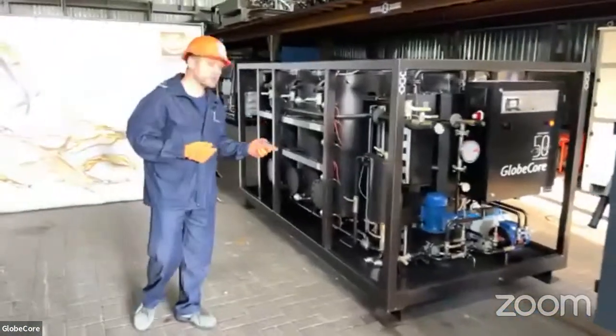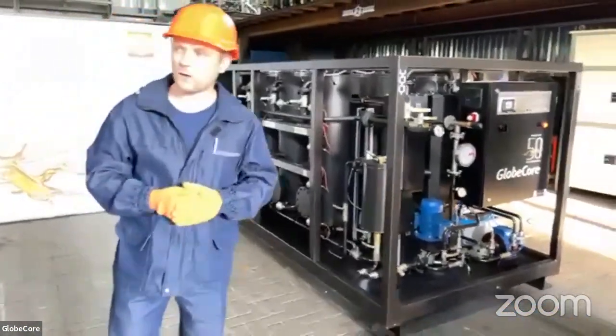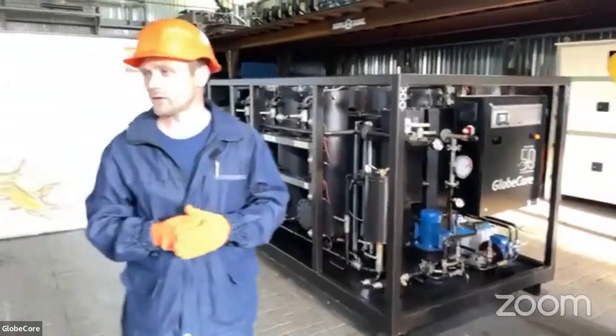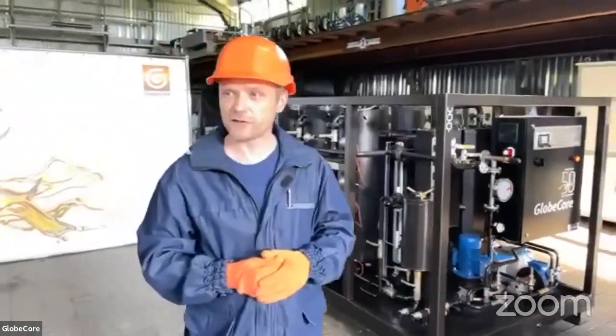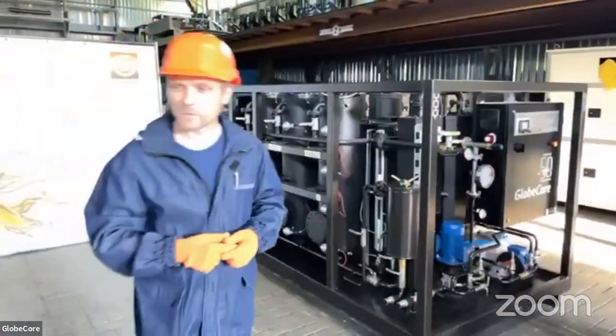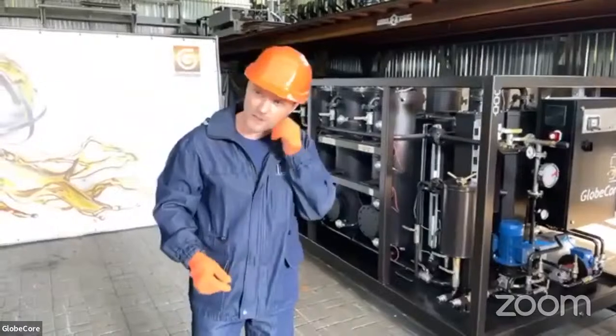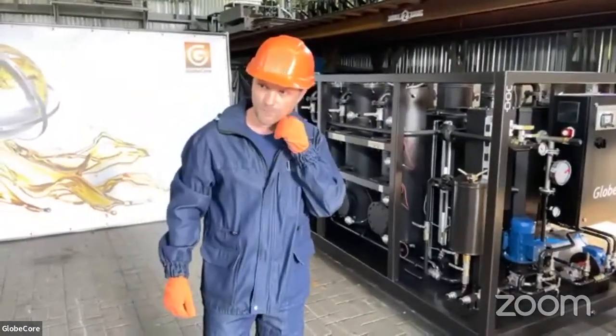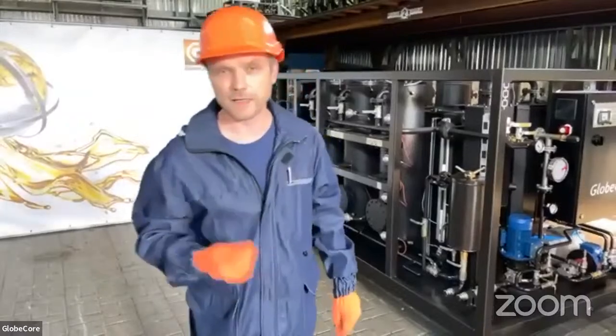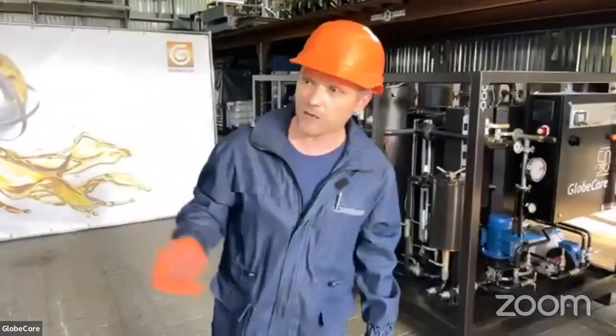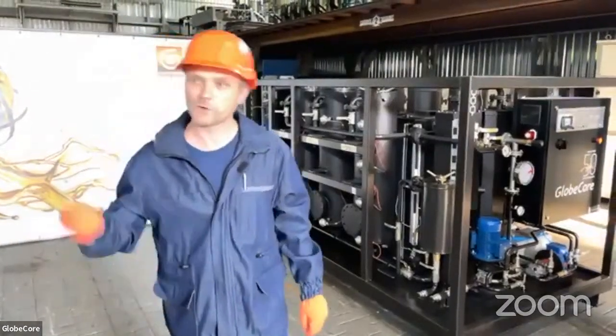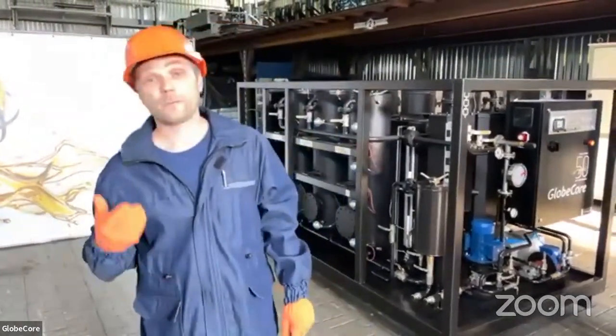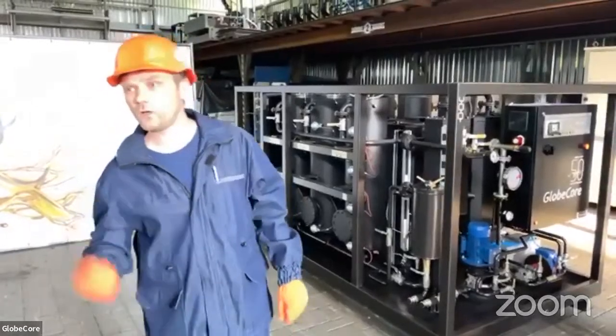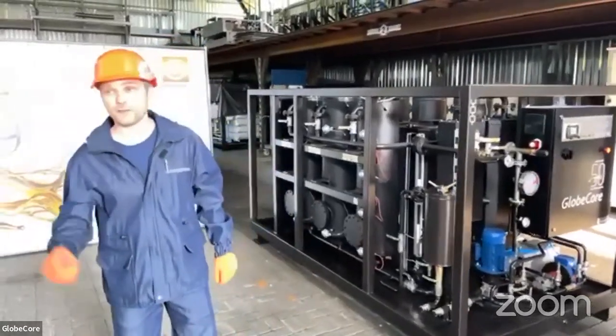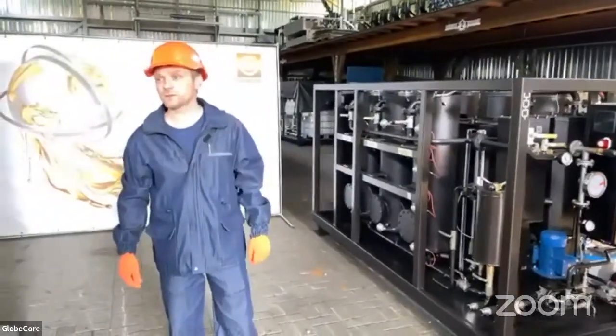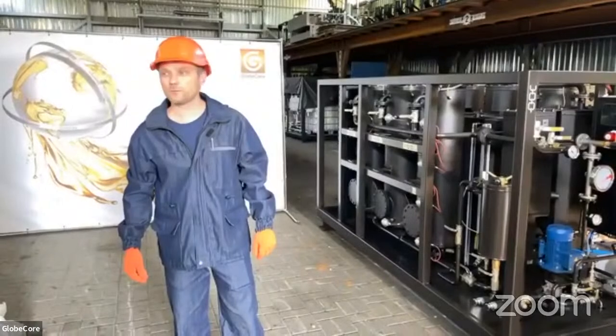And talking about the regeneration, we mean not only treatment of the oil, but treatment of that transformer as a whole, because we regenerate oil in cycles, which helps us to extract chemically aggressive components, not only from the oil, but from the insulation and from the sludge. So this technology affects not only the oil, but the transformer as a whole, and enables to extend the lifetime of transformer.